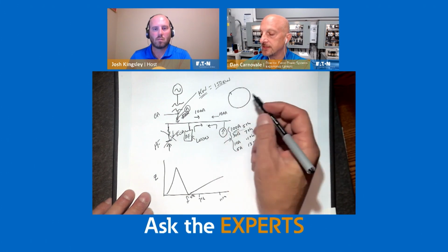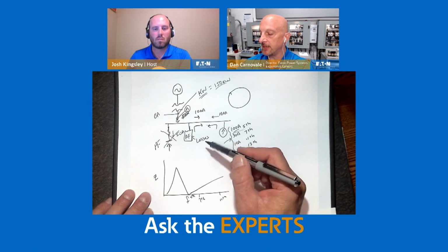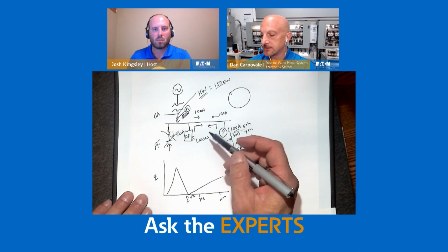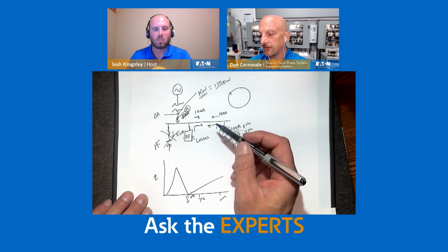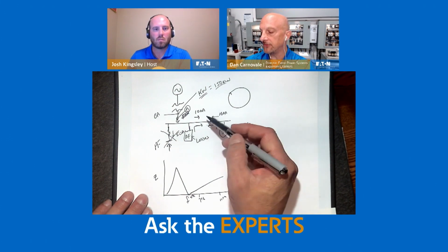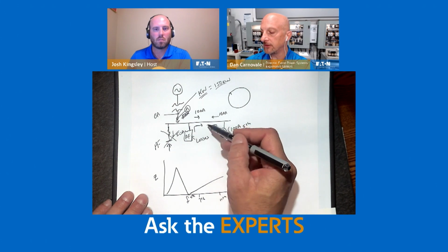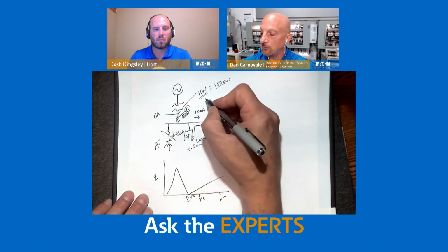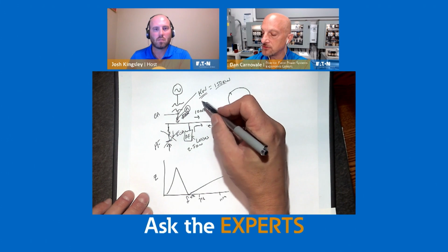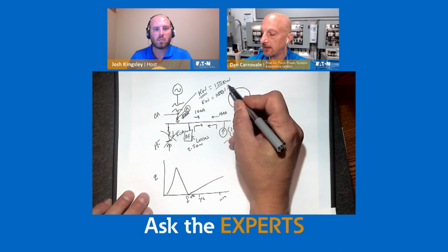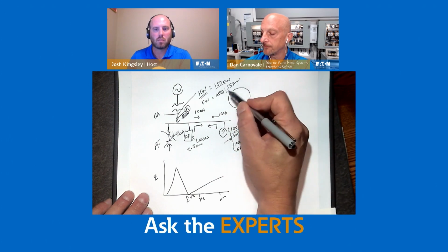And the reason they go up a little bit is because the current that you're taking out of here is not really real power, like kilowatts. It's similar to reactive power in the sense that it's distortion power. As that current's going through the system and getting corrected by this one, this actually might have, let's say, 2 to 5 kilowatts of losses. So the power that I measure on my system with that active filter on is 155 kilowatts.